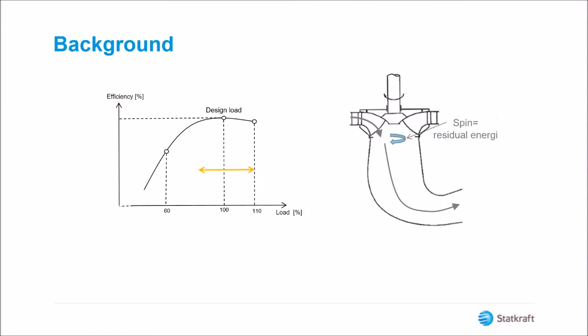However, as the load shifts away from the best efficiency point, more residual energy will be left in the water. This residual energy will result in a spin of the water in the draft tube.